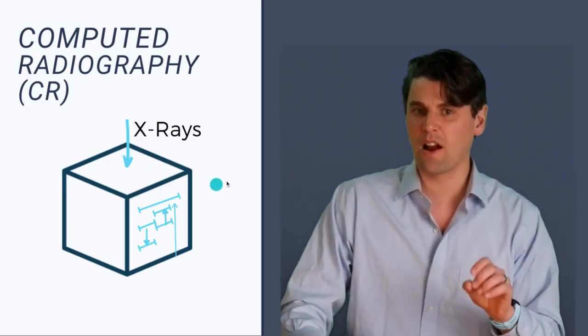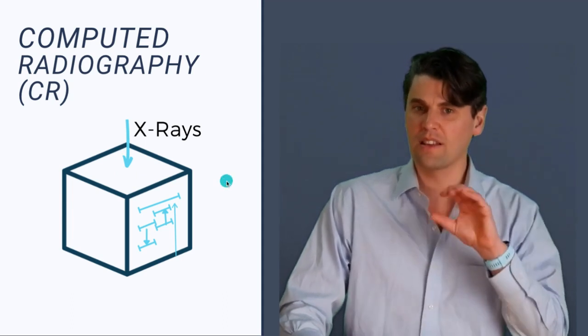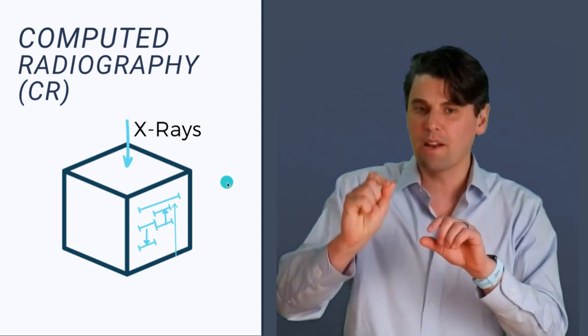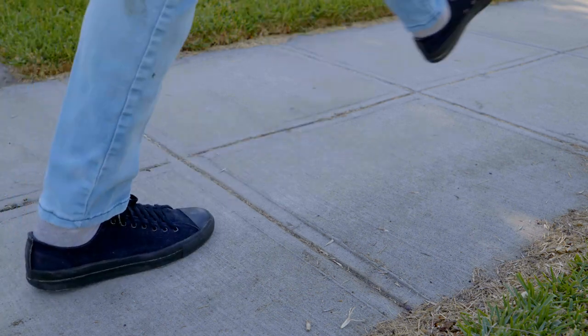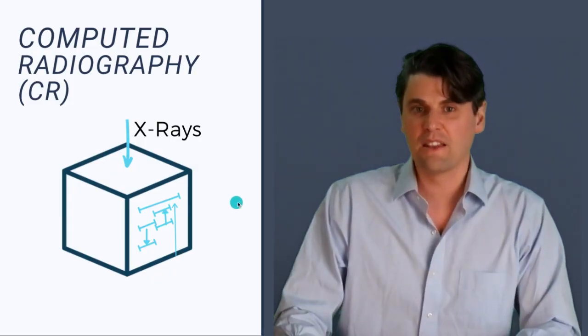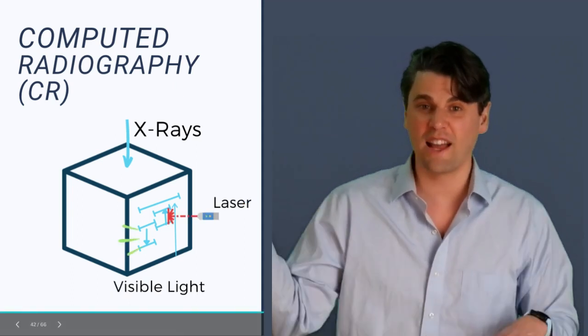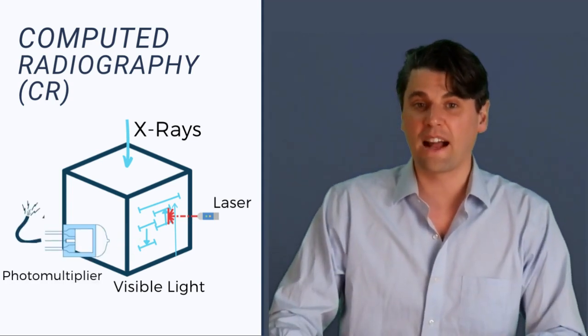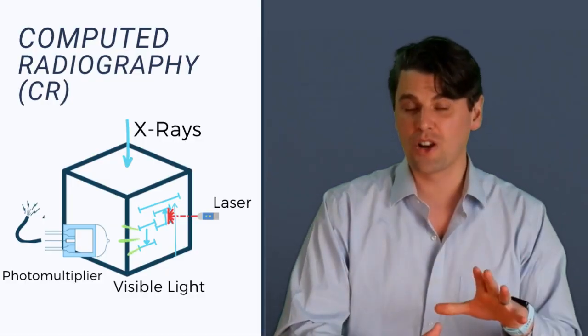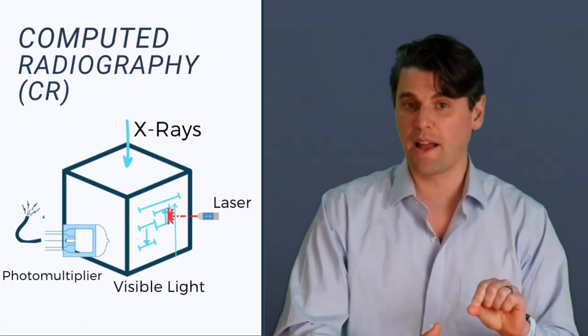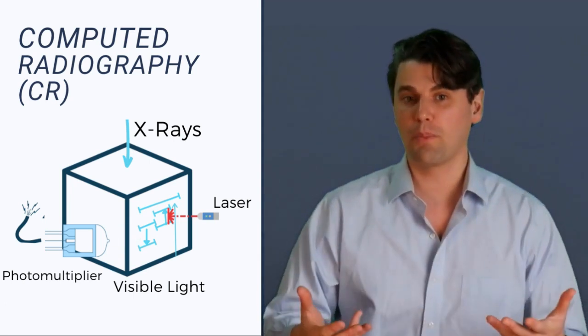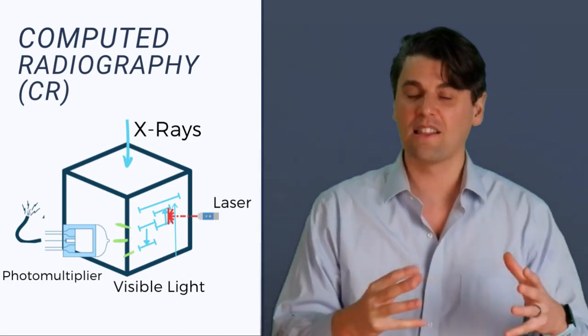So there is a latent image there. How do we free the latent image? There's actually some energy stored in the material, and in order to free it, we need to provide a little bit of a kick — basically shine a laser at the material. Once we shine a laser at the material, there is actually a separate light which is emitted. Then that separate light we're going to measure, and we're going to use what's called a photomultiplier tube in order to measure the light. When we're measuring light which isn't super strong, we want to use a photomultiplier tube to actually amplify that light signal.